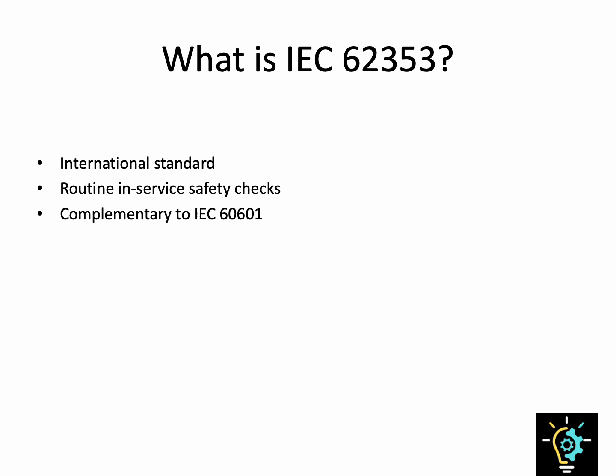So what exactly is IEC 62353? At its core, it's a framework for recurrent tests and tests after repair of medical electrical equipment. The standard came about because IEC 60601, the type test standard, was too complex and sometimes unsafe to apply outside a lab. IEC 62353 defines a set of practical, repeatable tests that can be applied during routine maintenance, inspections, or after repair.